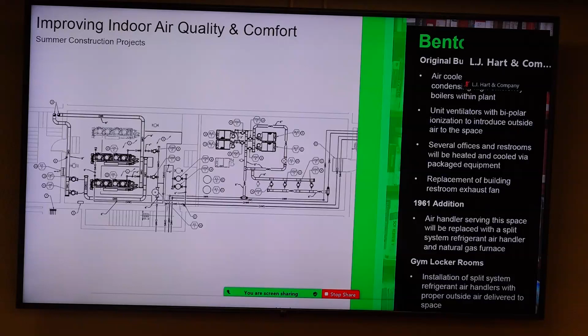Instead, we're going to use what's called a unit ventilator, basically a 2-foot by 8-foot piece of equipment typically located next to a window. It will have 4 pipes running to it, so one classroom could be in heating while another is in cooling, depending on need. It will also provide fresh air. To do that, we have to cut holes in the wall, installing a supply grill on the outside of the building, ducted into these unit ventilators, providing fresh air, cooling, and heating to each space.